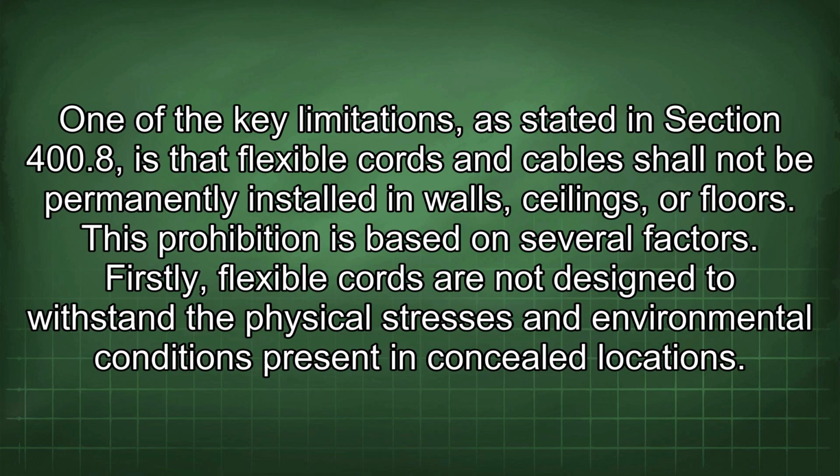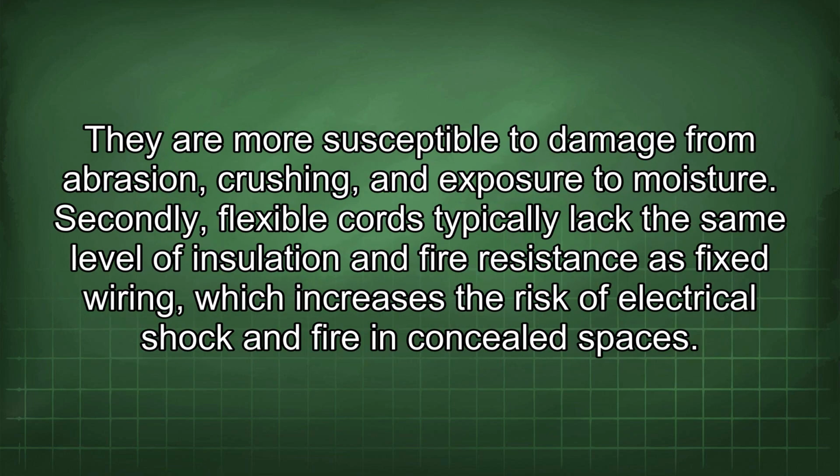One of the key limitations, as stated in Section 400.8, is that flexible cords and cables shall not be permanently installed in walls, ceilings, or floors. This prohibition is based on several factors. Firstly, flexible cords are not designed to withstand the physical stresses and environmental conditions present in concealed locations. They are more susceptible to damage from abrasion, crushing, and exposure to moisture.